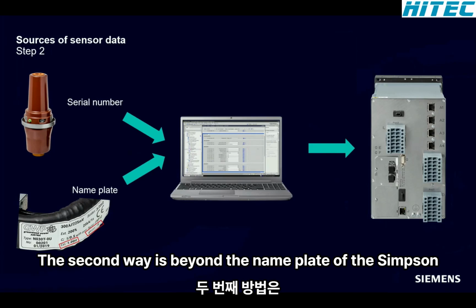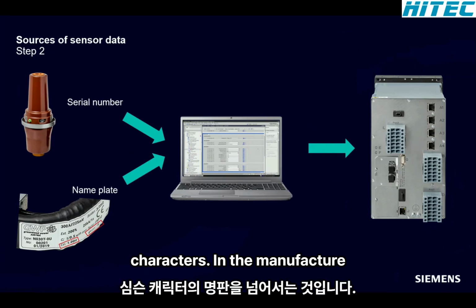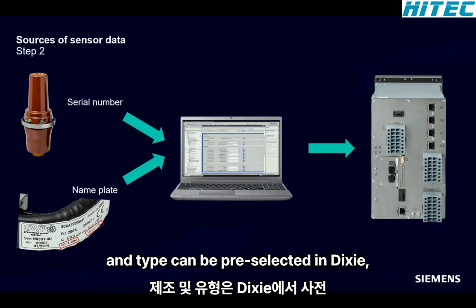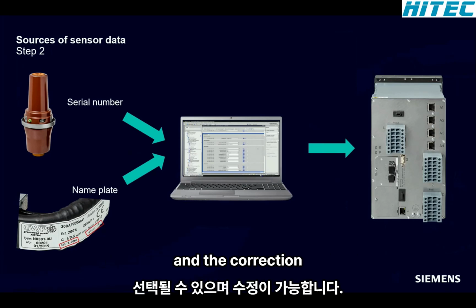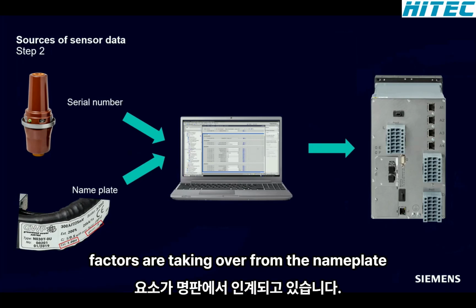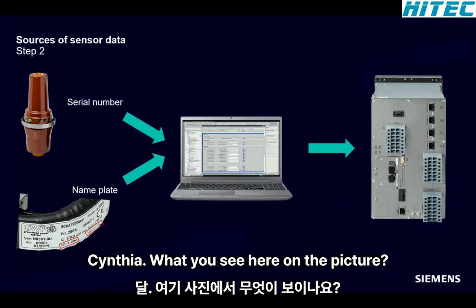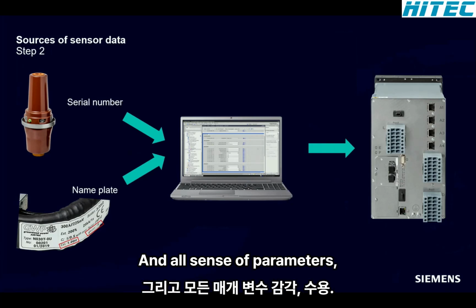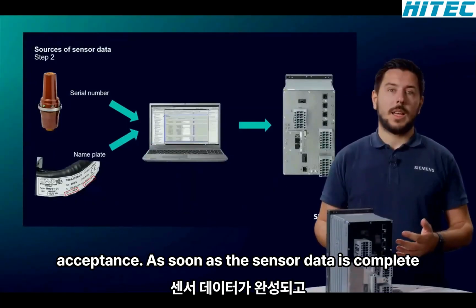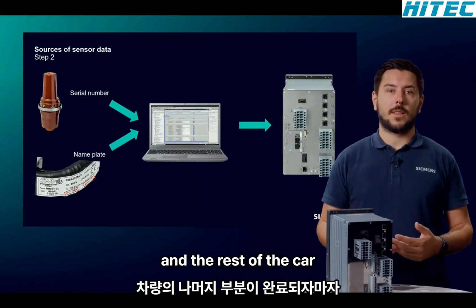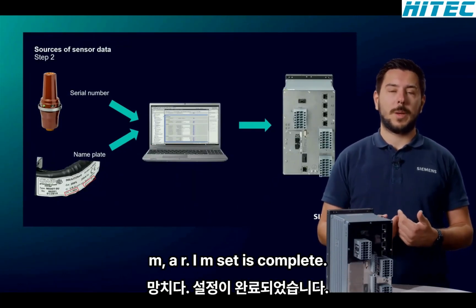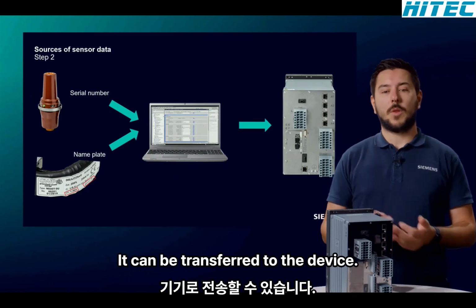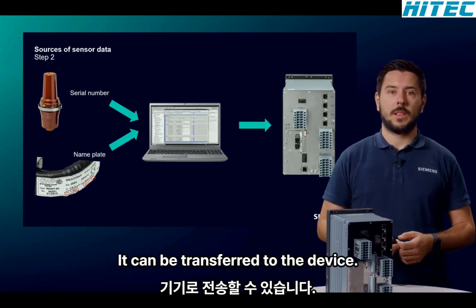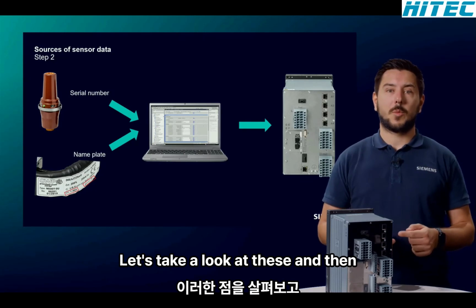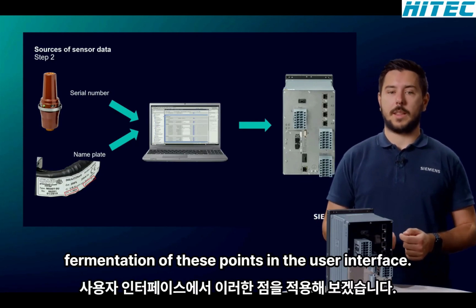The second way is via the nameplate of the sensor. If correction factors are specified for the sensor, then the manufacturer and type can be pre-selected in DIGSI, and the correction factors are taken over from the nameplate, similar to what you see here on the picture, and all sensor parameters are set then. As soon as the sensor data is complete and the rest of the parameter set is complete, it can be transferred to the device. Let's take a look at the implementation of these points in the user interface in DIGSI.